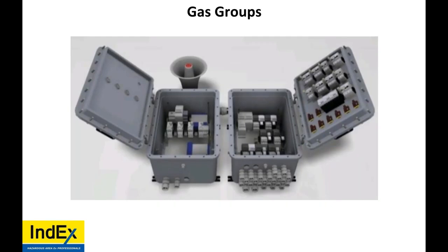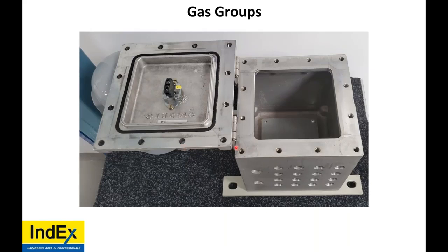This enclosure may look like a flange type, but get my laser working. If you look at the edge here, it goes into the enclosure. This is a spigot type enclosure. So the difference is on this flange type flat surface, within the standards, the restrictions are a very small enclosure for IIC, something of this size.